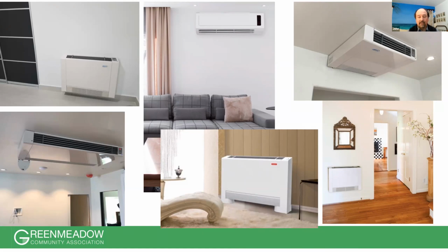Absolutely. If you're going to have a hybrid system, in terms of having a radiant floor heating system, to get the cooling we really need this added to it. And if you know what your boiler is set for, like 130, 140 degrees or higher, or 180, I already know that a heat pump is not going to be able to heat your house. We have to consider that the hot water from the heat pump could be 120 degrees or less in general for it to operate efficiently. And then it might bump up to 130, 140 degrees due to domestic hot water, but it's a temporary thing.